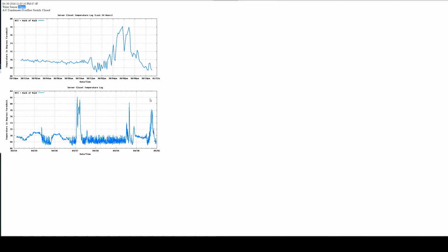On Friday, we wired up a backup AC system so that if our main AC fails, it will kick in and it will at least keep things from getting too toasty inside of our little data center. Here, it actually happens. So our trigger condition is 75 degrees for 5 minutes, and our backup AC will kick in.